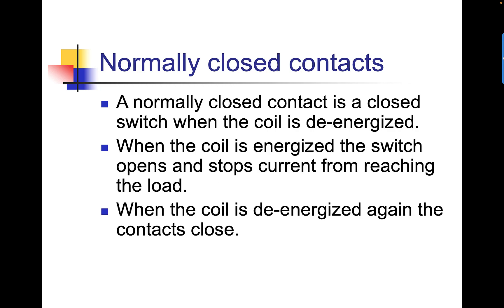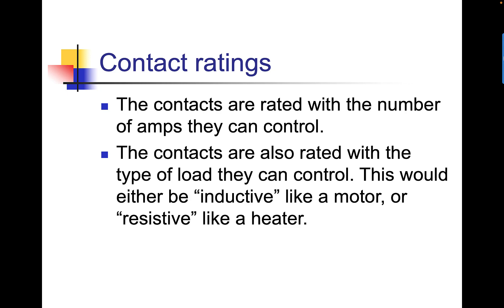Normally closed contacts are the exact opposite. They're closed when the coil is de-energized. In other words, the light switch is turned on when the coil is de-energized. When the coil is energized, the switch opens and stops current from reaching the load. When the coil is de-energized again, the contacts close again.